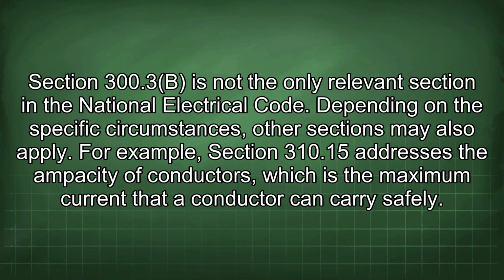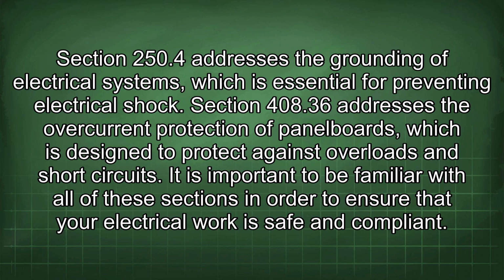Section 300.3b is not the only relevant section in the National Electrical Code. Depending on the specific circumstances, other sections may also apply. For example, Section 310.15 addresses the ampacity of conductors, which is the maximum current that a conductor can carry safely. Section 250.4 addresses the grounding of electrical systems, which is essential for preventing electrical shock. Section 408.36 addresses the overcurrent protection of panel boards, which is designed to protect against overloads and short circuits. It is important to be familiar with all of these sections in order to ensure that your electrical work is safe and compliant.